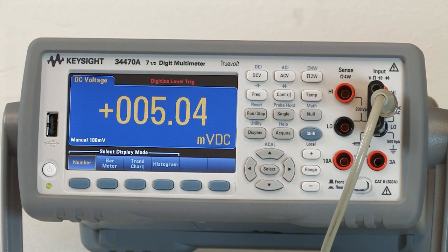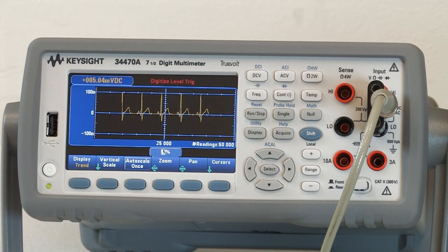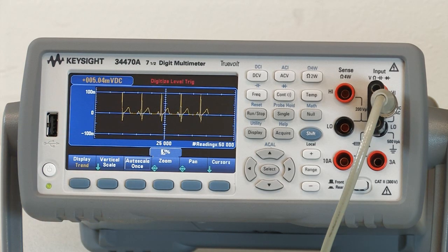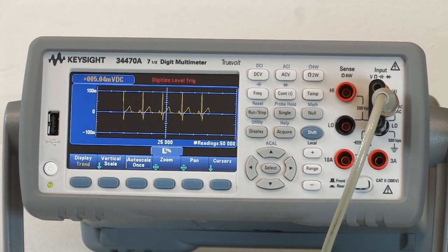Under Display, instead of number, I'm going to select trend chart. And it immediately brings up a graphical display of five cardiac waveforms coming from the arbitrary waveform generator.